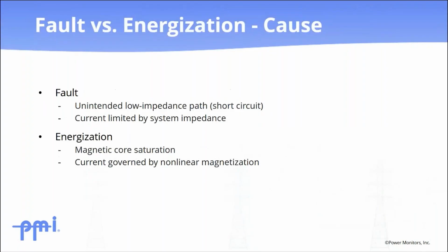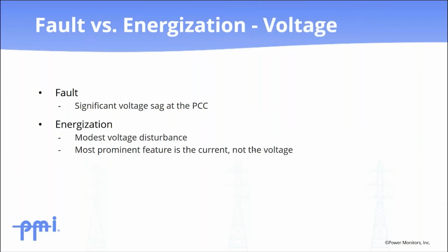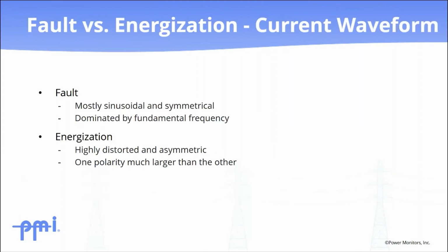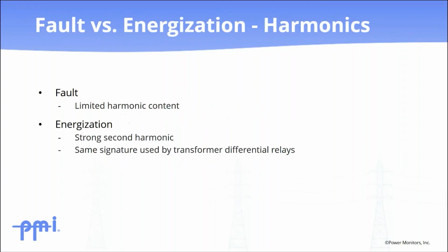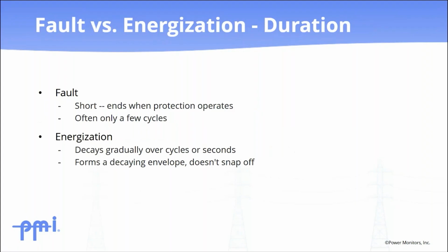In contrast, a transformer energization looks fundamentally different. The current is driven by magnetic saturation and not system impedance. The voltage disturbance is modest, especially on a strong system. The waveform is highly distorted and asymmetric. One polarity has much bigger peaks than the other. Harmonic content shows a strong second harmonic, and the duration is longer. The inrush decays over many cycles or seconds rather than ending abruptly.